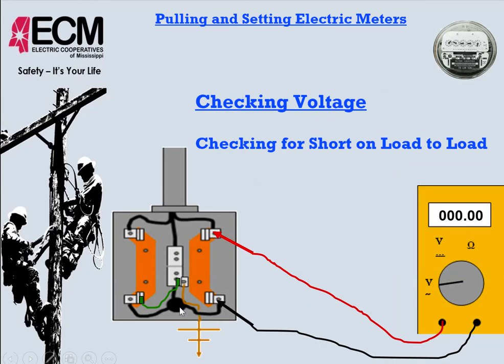Okay, the next thing we want to check for is making sure that our load side is not shorted together or tied together. There are two ways that we can do this. We can take a short piece of wire and ground one side. If the two load side lugs are tied together inside by a device, or the wires twisted together, or a nail nailed through a piece of conduit or a piece of Romex, if we ground one of them, we would essentially be grounding both of them.